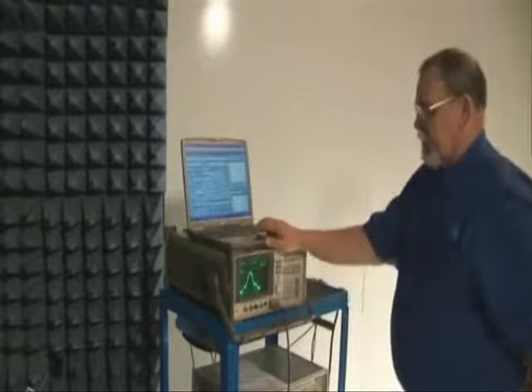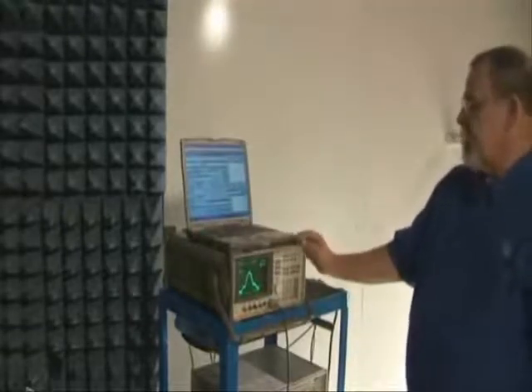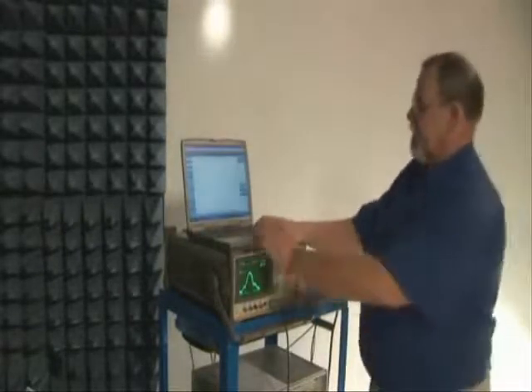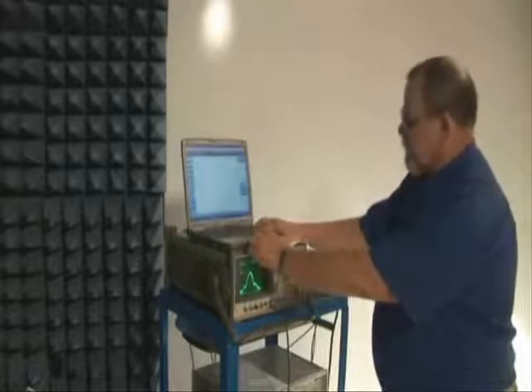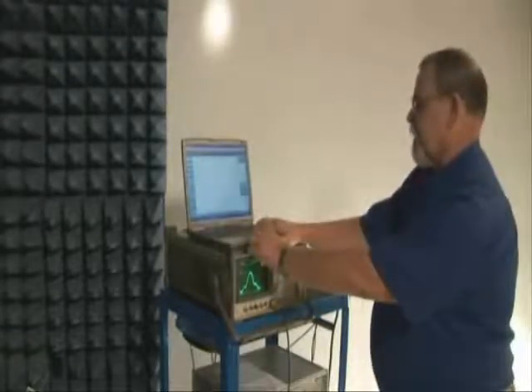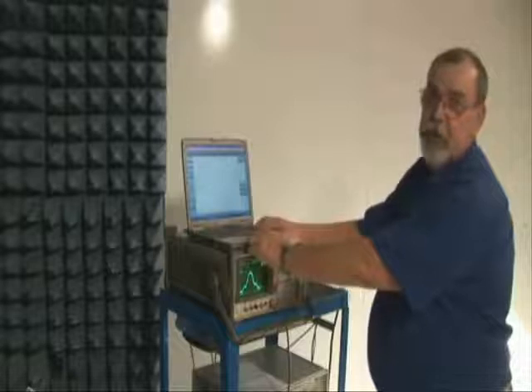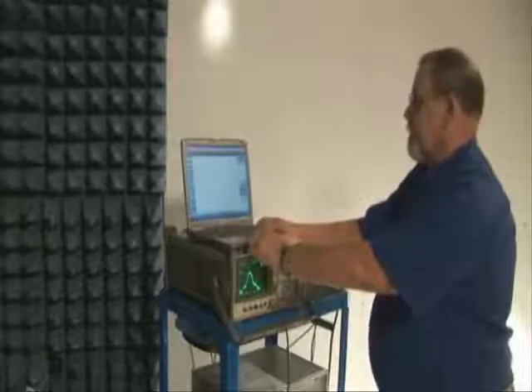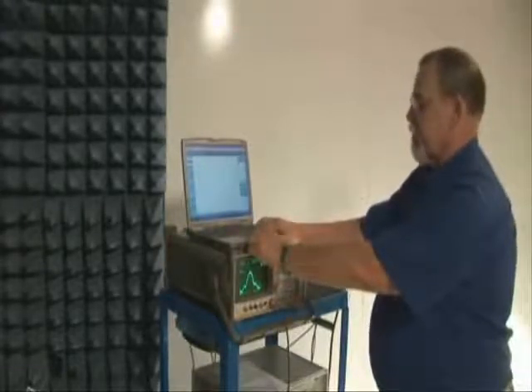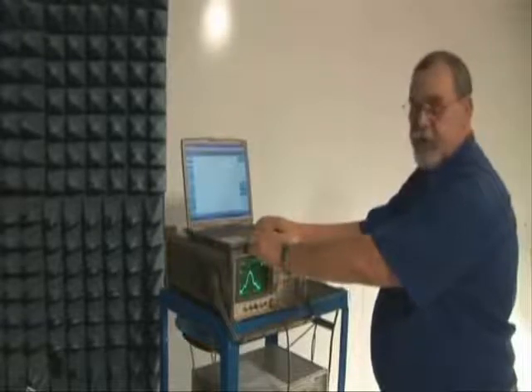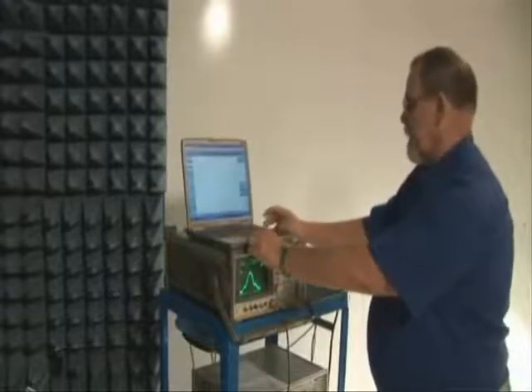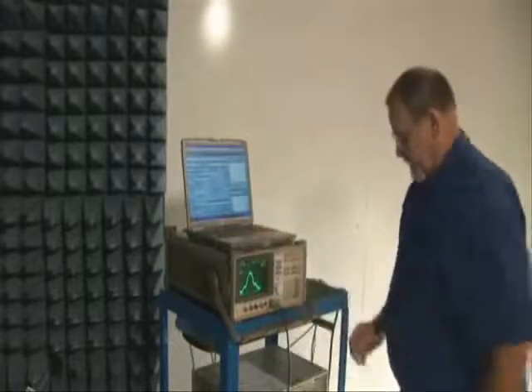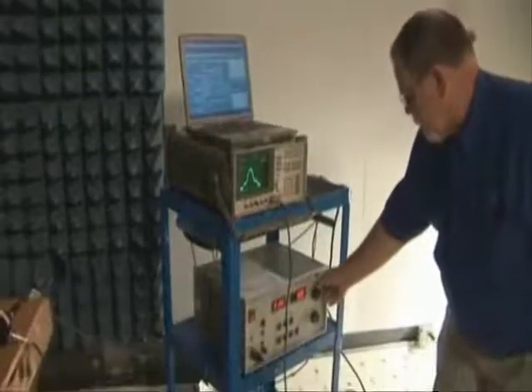And we execute this frequency and collect the data. And we plot that this measurement is now, in fact, 6 dB below the limit. It's measuring closer to 7, but it's well within our tolerance of plus or minus 3. So we're saying that this system is working very well. Our next frequency point would be to go ahead and collect the data for 10 kilohertz. So let us do that.